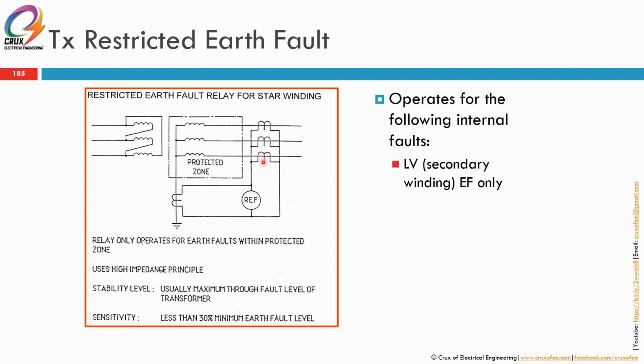This one, red, yellow and blue, will sum and this will come up with the zero sequence current for these three phases. So under normal condition, these two CTs, this CT and these three CTs are looking into the winding. So under normal condition, when there's an earth fault external to this, both all the CTs will look, but they will cancel each other lah. So there will be no detection of earth fault within this zone. So this uses a high impedance principle. So normally there will be a high impedance resistor here within in series to the REF.